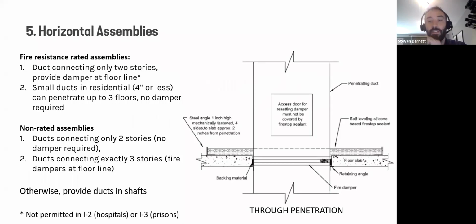Now, the first thing to note on this slide is the graphic on the right. That's called a through penetration because the duct is penetrating fully through the floor. And so if the floor you're penetrating is fire resistance rated and the duct is connecting only 2 stories, provide a fire damper at the floor line. That is permitted. There are also, in residential, for small ducts 4 inches or less, you can penetrate up to 3 floors with no damper required. Those are fire resistance rated floor assemblies.